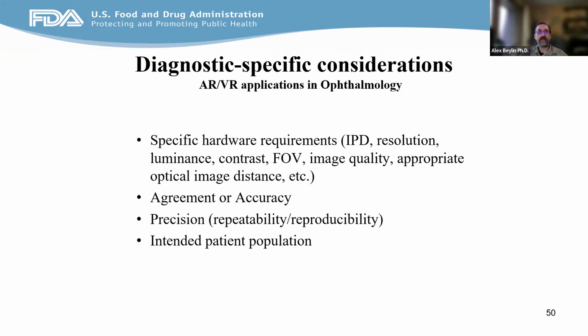Diagnostic devices that use AR/VR technology present additional challenges to developers. These challenges may include hardware requirements specific to the device's diagnostic functions. If the device performs measurements, agreement or accuracy of the measurement should be demonstrated. For these devices, precision, which may include repeatability and reproducibility, is necessary to study variability of the measurement.